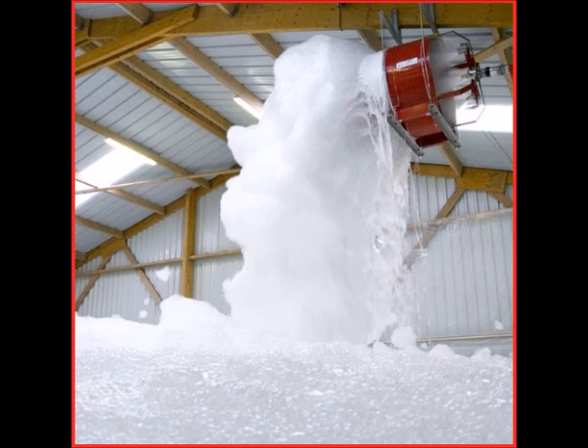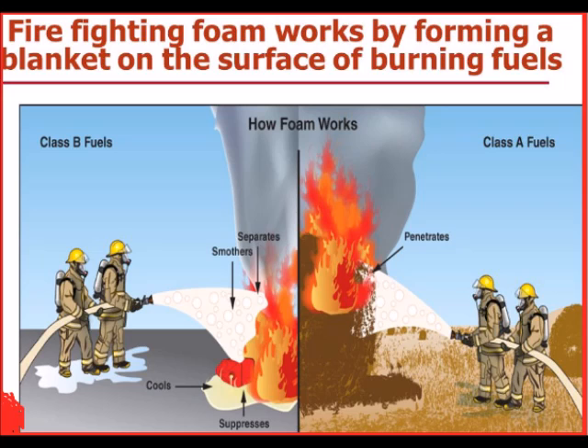Aqueous film-forming foams (AFFF) are resistant to the action of alcohols and can form a protective film. Protein foams contain natural proteins as the foaming agents. Unlike synthetic foams, protein foams are biodegradable. They flow and spread slower, but provide a foam blanket that is more heat-resistant and more durable. Protein foams include regular protein foam (P), fluoroprotein foam (FP), film-forming fluoroprotein (FFFP), alcohol-resistant fluoroprotein foam (RFP), and alcohol-resistant film-forming fluoroprotein (RFFFP). Protein foam from non-animal sources is preferred because of the possible threats of biological contaminants such as prions.